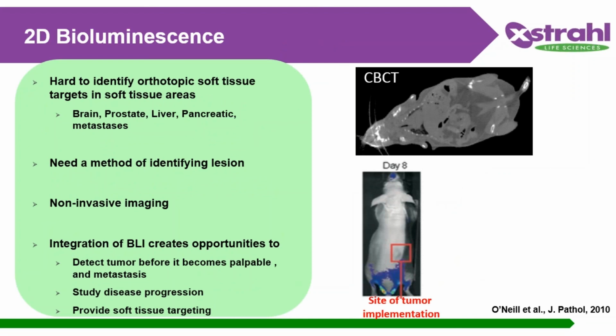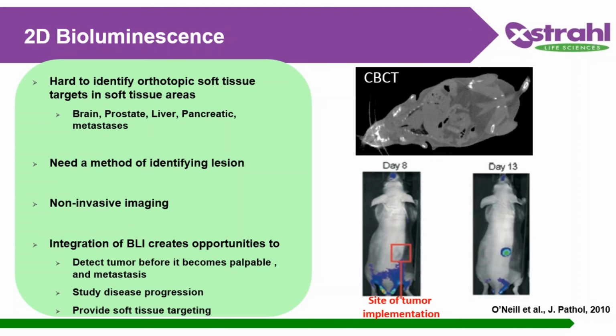So we developed MiraGlow. It is a three-dimensional optical system with a rotating mirror assembly that captures light intensity from all the way around the animal. It has a high-resolution cooled CCD camera, charge-coupled device camera, that records precisely the emitted light. It has reconstruction protocols and algorithms which convert the light intensity data into a center of mass that becomes your isocenter. The system may soon accept a fluorescent camera, and this is currently in development.